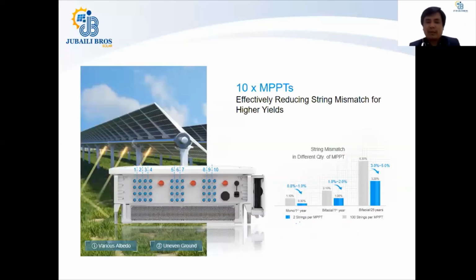Okay, so Huawei with this new inverter having 10 MPPTs gives you the benefit of fewer losses in terms of mismatches. As you know, in the PV system, there can be various albedos, there can be uneven ground, there can be uneven soiling even on the different segments of your PV system. With these types of factors reducing the installation output, these can increase with time if you do not use proper machinery, or a proper inverter I would say, which can reduce the effect of such mismatches.